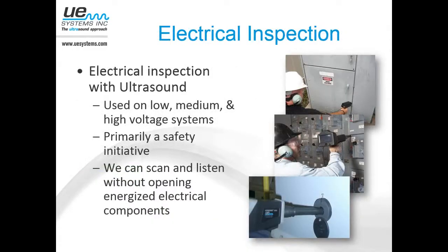All right, I'm going to switch gears and talk about electrical inspection with ultrasound. It's become, over the last several years, a major application. Most people think of their electrical distribution system in the plant, or their substation outside the plant, as a place to use infrared. But the interesting thing is if you look at different failure modes of electrical apparatus, there's a distinctive type of failure mode that infrared will detect, and a whole separate set of failure modes that ultrasound will detect.